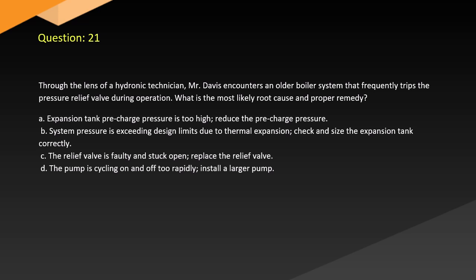Question 21. Through the lens of a hydronic technician, Mr. Davis encounters an older boiler system that frequently trips the pressure relief valve during operation. What is the most likely root cause and proper remedy? A. Expansion tank pre-charge pressure is too high, reduce the pre-charge pressure. B. System pressure is exceeding design limits due to thermal expansion. Check and size the expansion tank correctly. C. The relief valve is faulty and stuck open. Replace the relief valve. D. The pump is cycling on and off too rapidly. Install a larger pump.